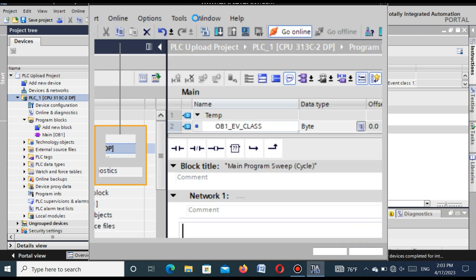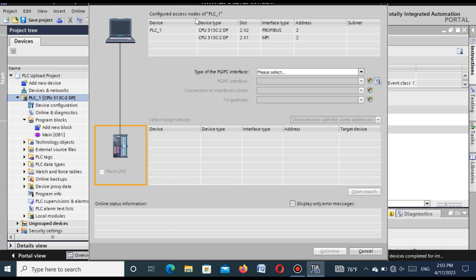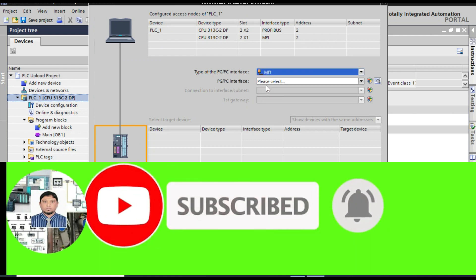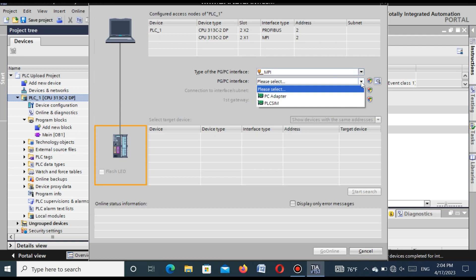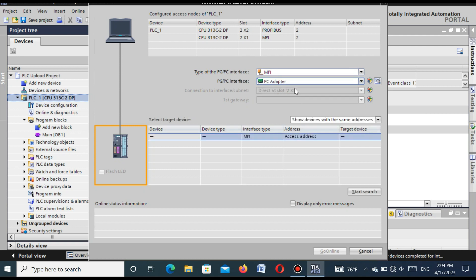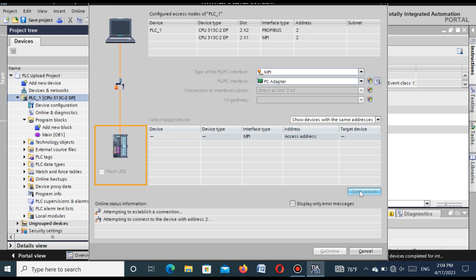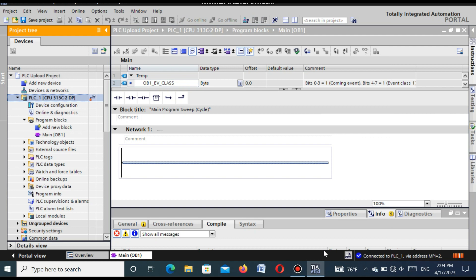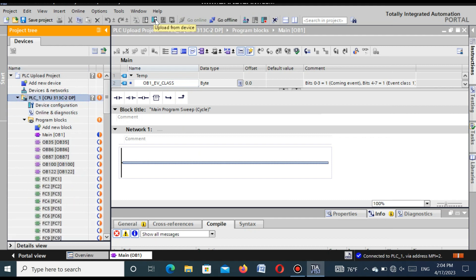The communication between the PLC and the laptop is confirmed. Now select the CPU and go to 'Go Online'. Here you can see the CPU connected with the laptop. Select the combination cable MPI and set the PG/PC interface to 'PC Adapter'. Press 'Start Search'. After searching, it accesses the CPU. Select the CPU and press 'Go Online'. You can see the CPU is now online with the TIA Portal software. Now select the CPU and press the 'Upload from Device' button to upload the program from the CPU.